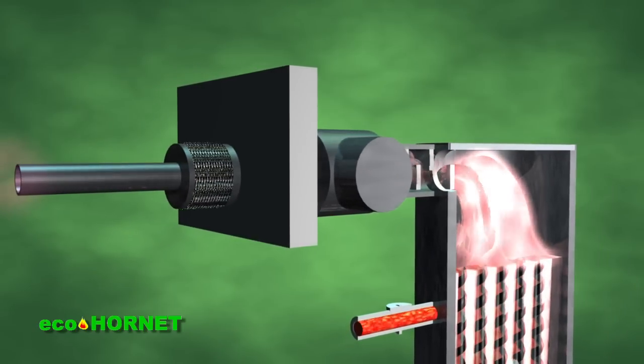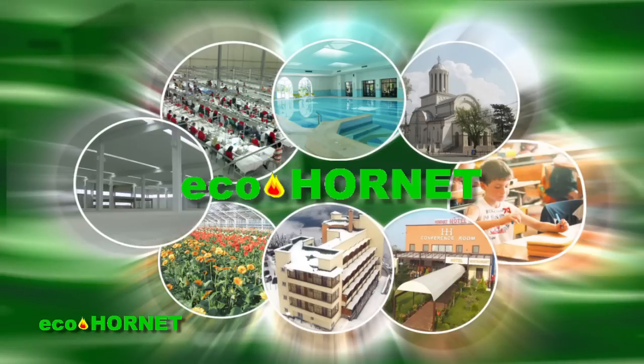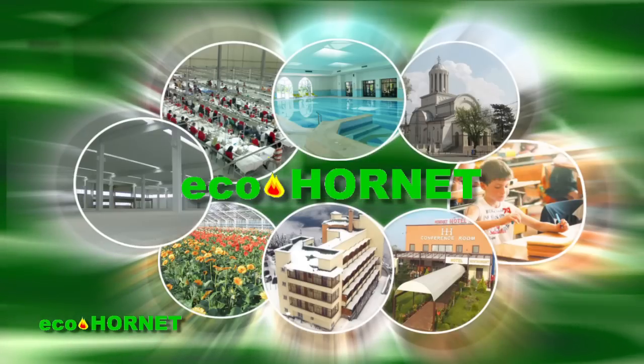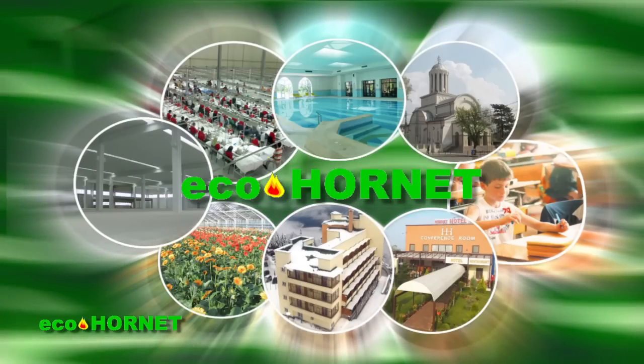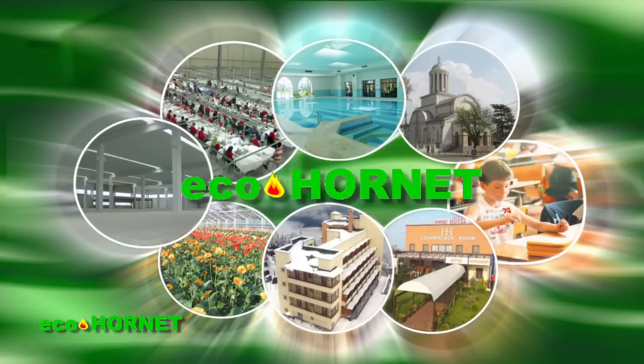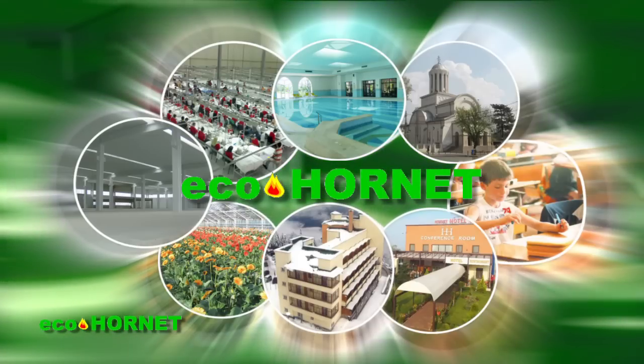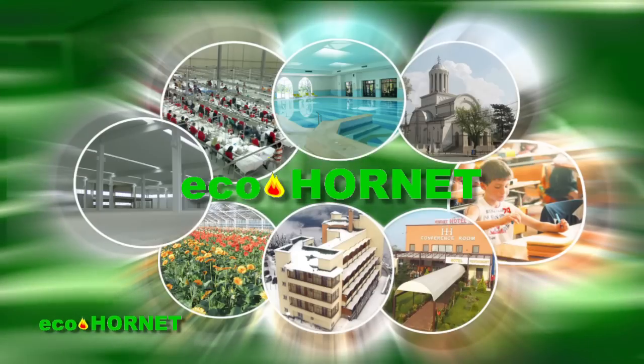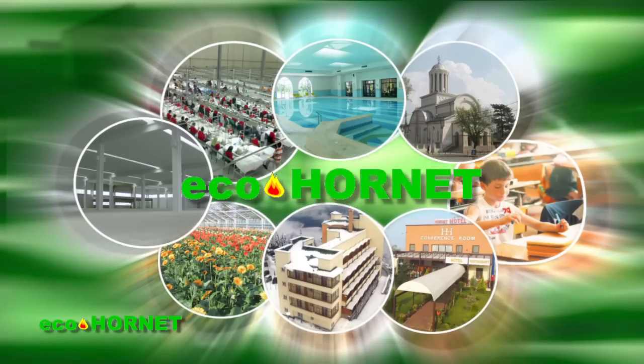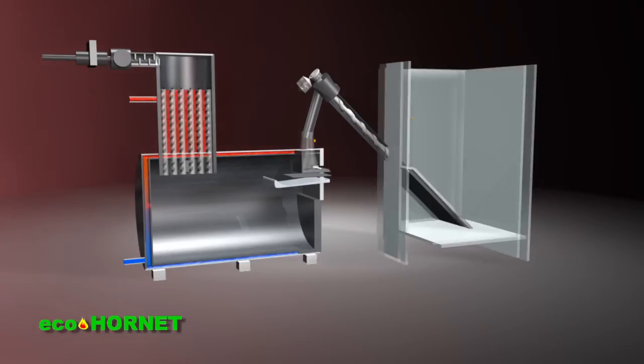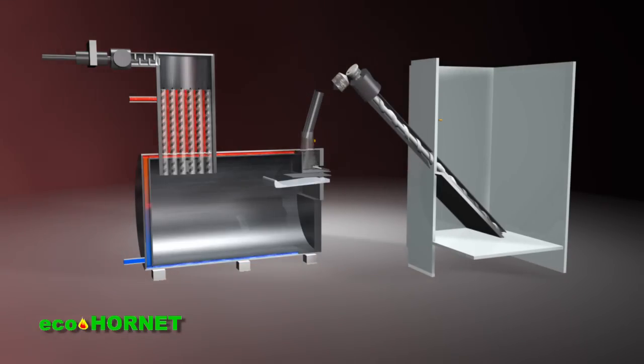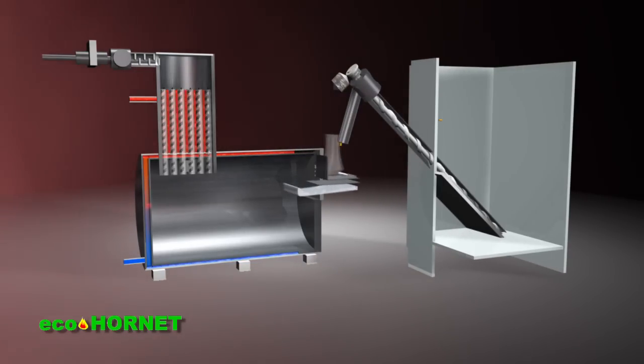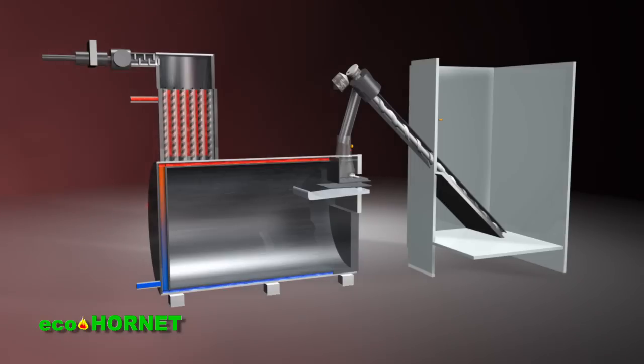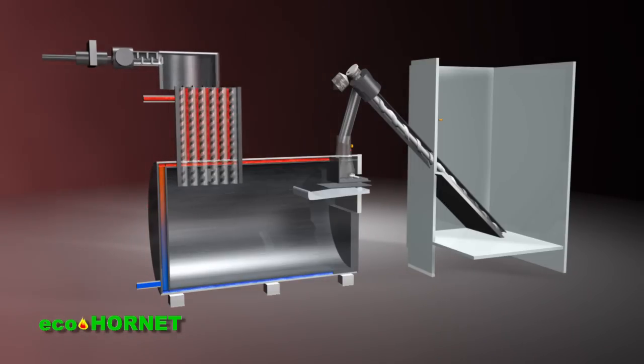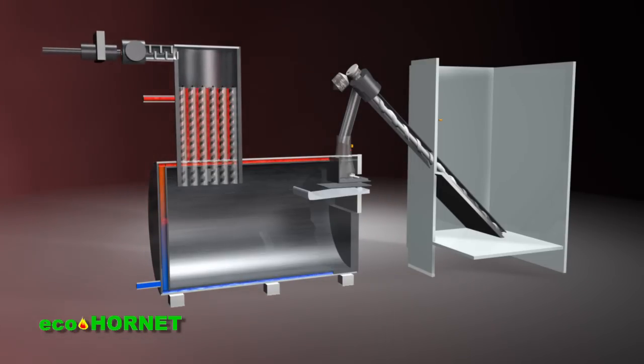smoke and ash particles. The EcoHornet products target all areas of activity, producing heating agent for both home users and for large spaces, such as industrial spaces, greenhouses, gymnasiums, swimming pools, churches, hotels, schools, etc. The EcoHornet heating system consists primarily of the following: pellet bunker, worm gear, feeding tube, combustion chamber, horizontal heat exchanger and ash bin, vertical heat exchanger, exhaust, gas exhaust tube, command panel.